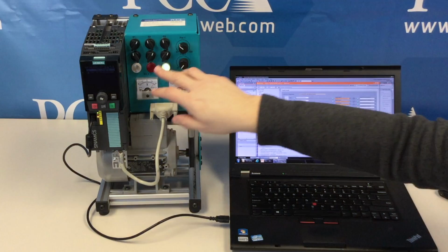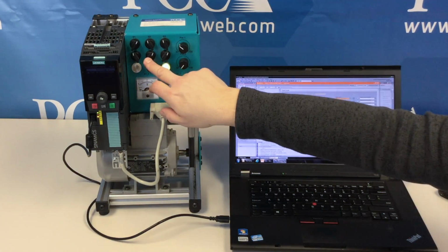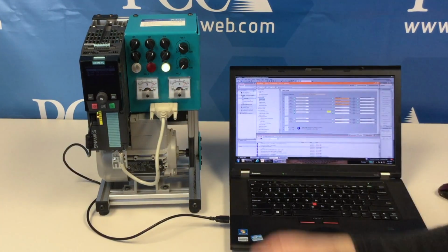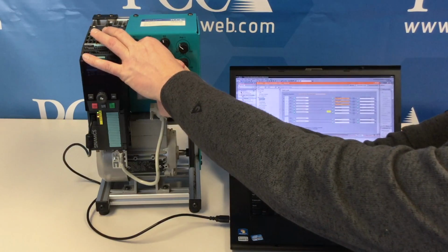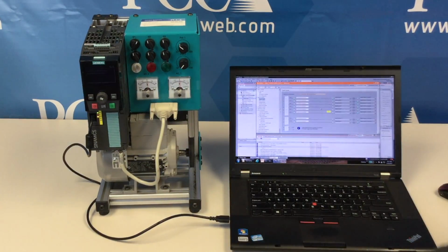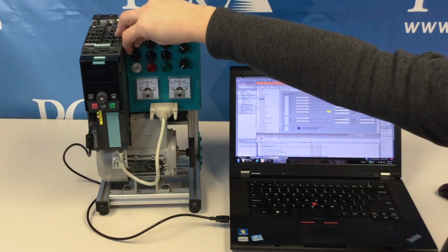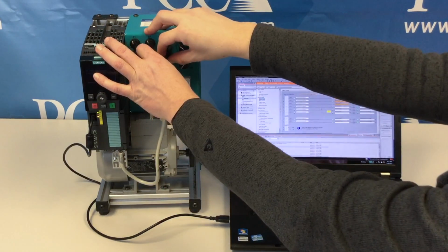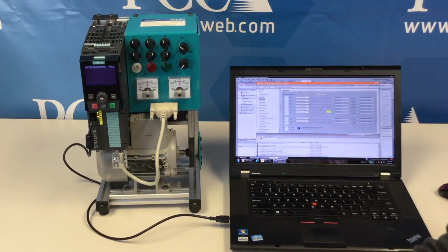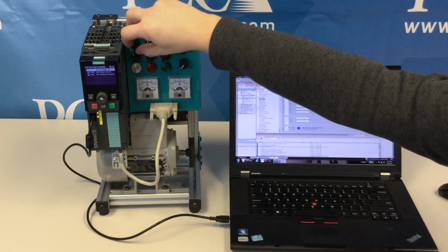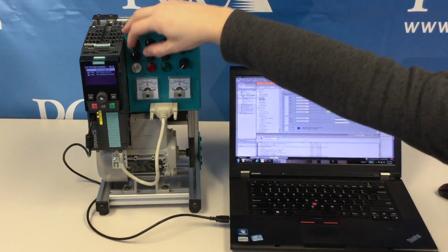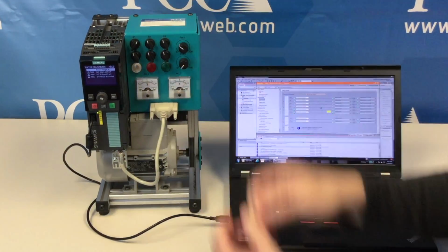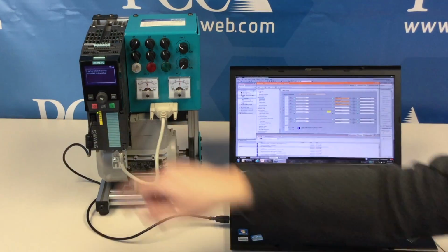And then my switches, my digital input 4 and 5, which is switch 5 and 6, actually, are my safety circuit. So when I switch those two off, simulating an e-stop, I go into safe torque off mode. Now I cannot start my drive. I can reset my safety circuit by pulling the safety circuit button back out, turn those digital inputs high, and now my solid amber light. Run the drive again, safe torque off, which is indicated by the blinking amber light.